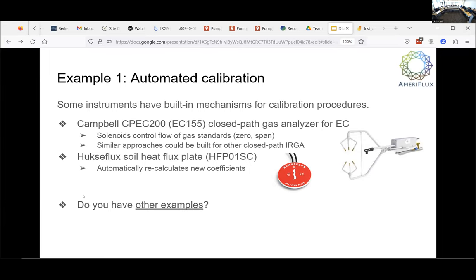So that's part of the conversation we should all have, right? I mean, oh yeah, I noticed that I did a calibration, I looked at the new calibration coefficients and what the difference is, what the heck is this? I probably did something wrong. They do change, but they don't change drastically, right? And for different sensors, we have all had experience about which part of the calibration we should be paying attention to.